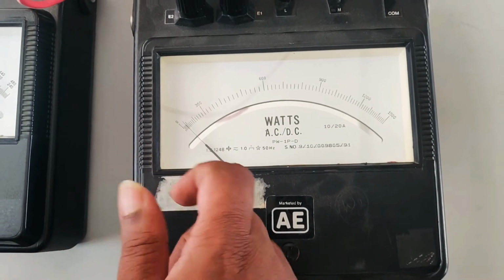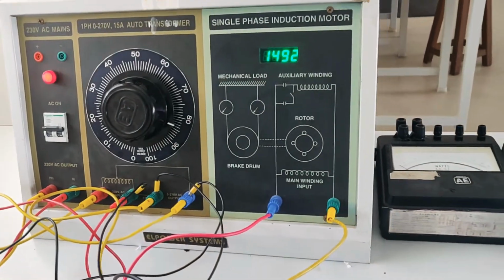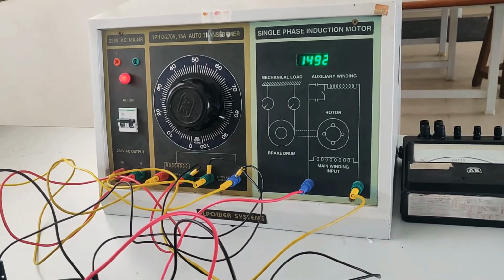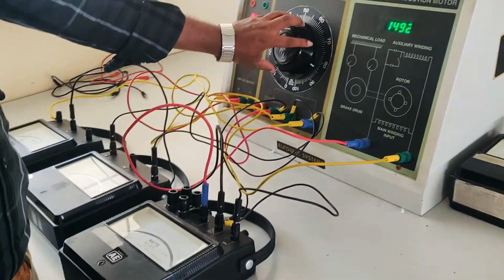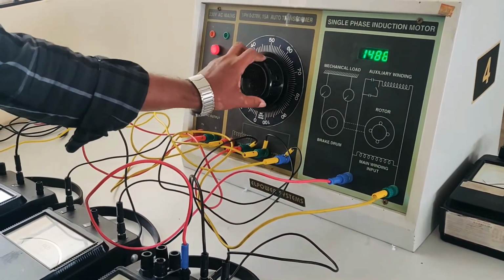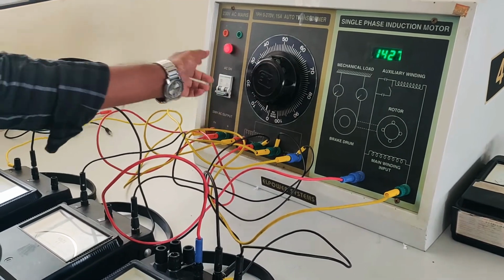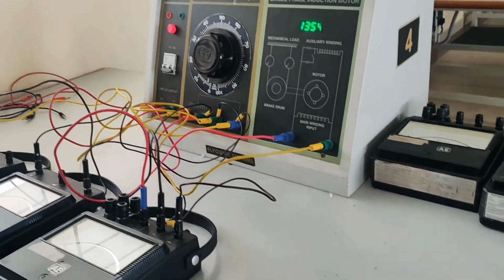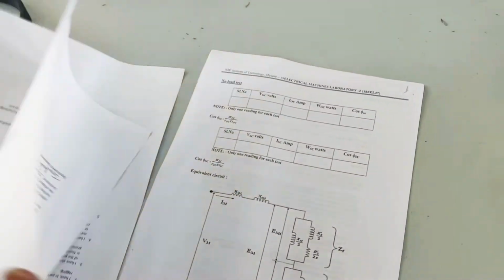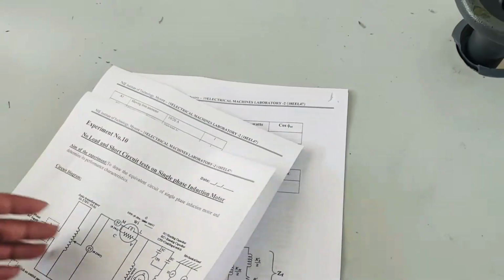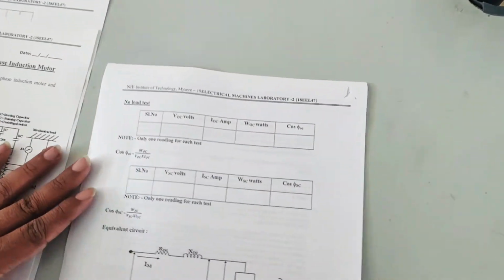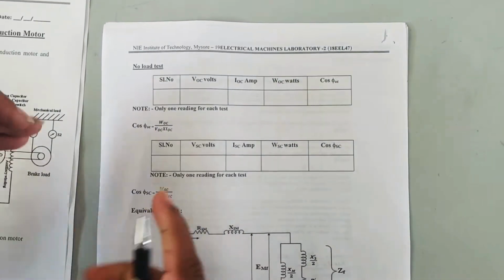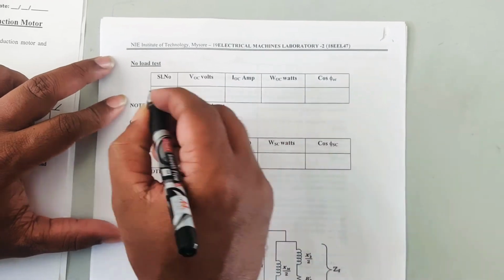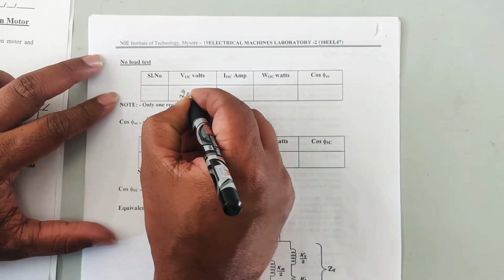Okay, so this is how you have to conduct the no load test. After conduction, the first thing is you have to reduce the auto transformer to 0, and then switch off the MCB. Only 3 readings you will be taking, keep it in mind. The first reading is V0, the second one is I0, and the third is W0. V0 is 230 volts and I0 is 6.8 amperes.